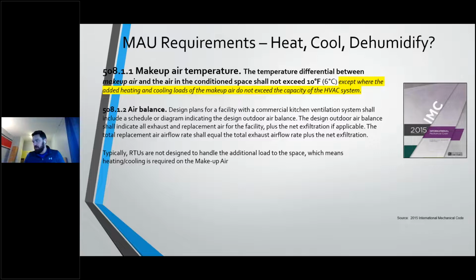And the answer is, and I know when I was brought on today, it was, hey, what are you guys seeing in packaged DX cooling? I think up in your area, it's just that summers are getting hotter, so people are wanting cooling in the system. And if I'm being completely honest, there isn't a hard and fast rule across the country. Packaged DX cooling is absolutely used in a lot of kitchens across the country, and it accomplishes this exact same thing. It gets the air to within 10 degrees of the conditioned space, but it doesn't dehumidify. And it has a large cost associated, versus just the standard heat-only makeup air.